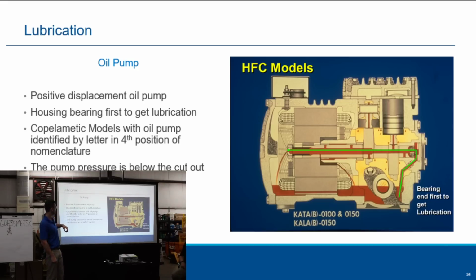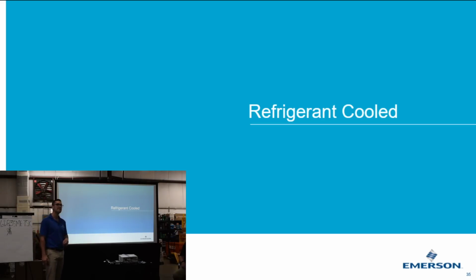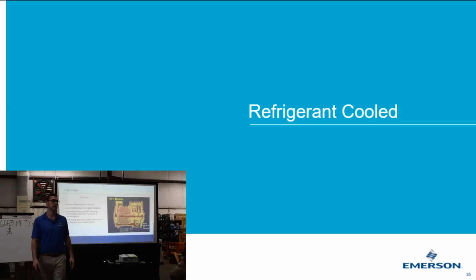Positive displacement. One thing that you don't see on these compressors is an oil pressure switch, the oil safety switch, because the oil pressure is below the cutout. So what happens if there's a problem with the pump? Well, then you're going to run into an issue with the compressor, but you won't have an oil safety switch on it. So you'll have to pull it apart and find out if it's an oil problem. You would only know after the fact, like your compressor seized. Like I said, there's no cutout switch on these smaller ones.